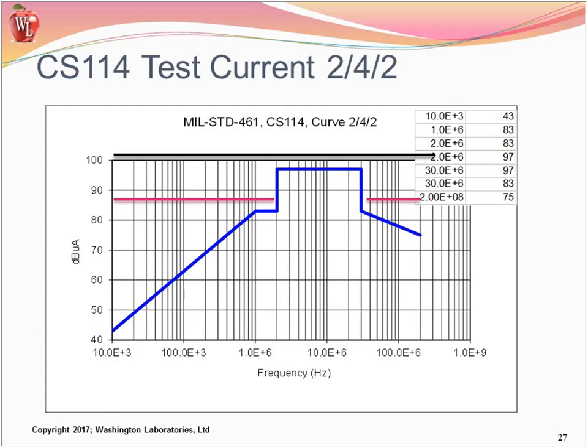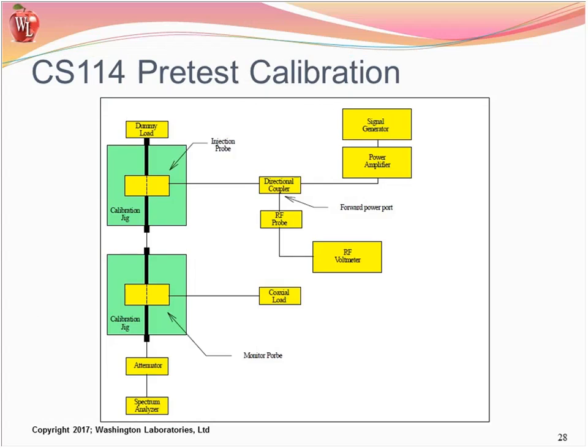So if I have a current that's got 3 levels going on here, I had the test current. At frequencies below where the curve 4 applies, would we use 6 dB above across the whole board, or would you use 6 dB above the highest point for the curve 4? It's indicated in the standard that you'd use the red line and then the black line for that band for curve 4, and then come back to the red line for the portion that's above 30 megahertz. That's the way the words read. So make sure you interpret it using that kind of philosophy.